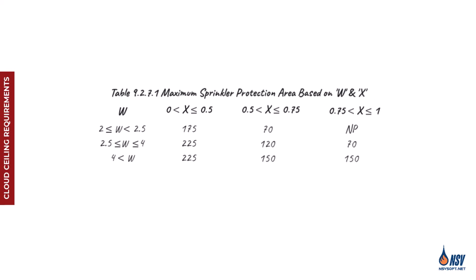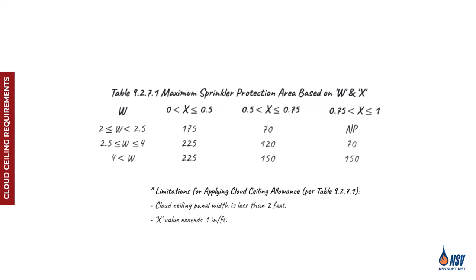Table 9271 contains two hidden limitations that are easy to overlook. First, if we examine the width values listed for cloud ceiling panels, none fall below 2 feet. Second, when reviewing the range of x values, no options exceed 1 inch per foot. These omissions signal that in both cases, panel widths under 2 feet or x values above 1 inch per foot, the table does not permit cloud ceiling allowances to be applied. Therefore, the option to eliminate sprinklers above the cloud is no longer valid.